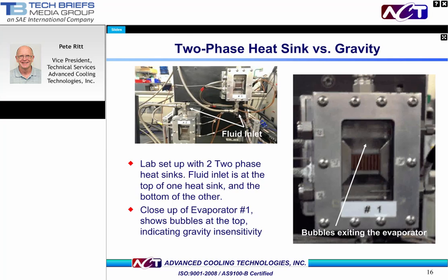A close-up of evaporator number 1, seen on the right, shows the flow against gravity. Inlet flow is liquid at the bottom, and bubbles are seen exiting as the working fluid exits the evaporator at the top, indicating pump 2-phase systems can be implemented in any orientation.